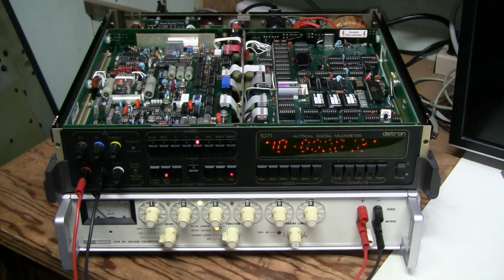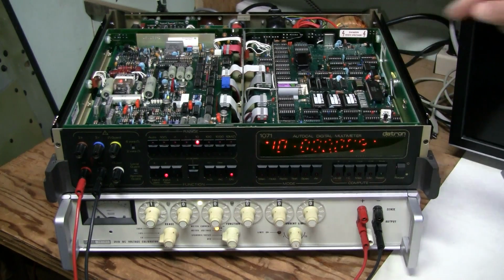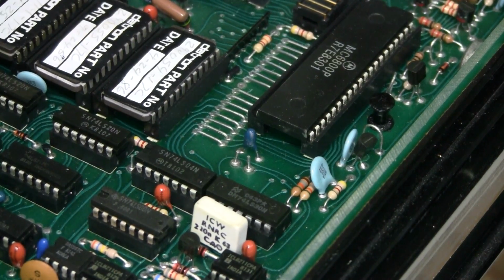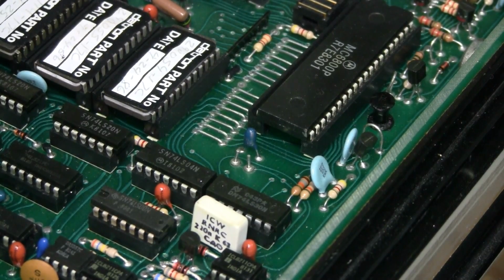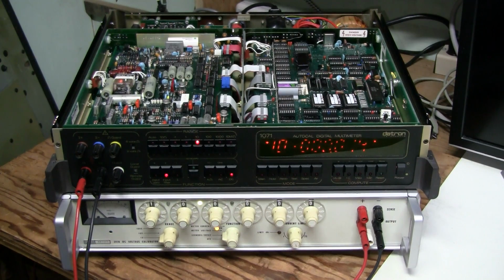So I found a procedure how to clear the calibration parameters. There are two pins here next to the processor. They need to be shorted when the meter is powered up, and that clears the calibration parameters. After doing that, the meter powers up with no error messages and seems to work just fine. So I started going through the post-repair adjustment procedure, and my first idea was to use this Fluke calibrator, even if it's not really sufficient for the job, because it is just 6-digit and, simply speaking, 50 ppm unit.